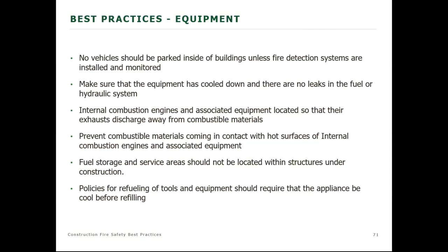And fuel storage and service areas should not be located within structures under construction. The fire in Denver that killed the 2 workers, they think they couldn't prove it, but they think they were improperly refueling equipment, and that's how the fire started and spread so quickly. Waste materials, there should be scheduled delivery as close to installation as possible. Everything should be kept clean. You want to cut back the vegetation 60 feet if you can, and prohibit open fires.